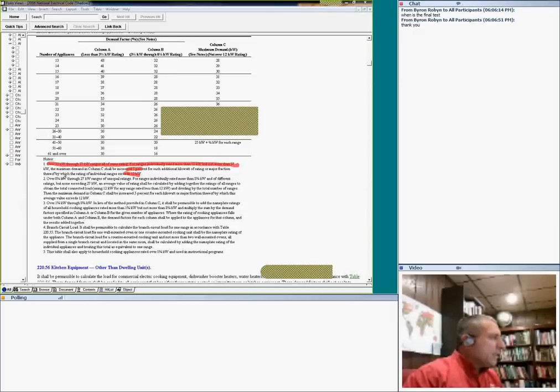If they are different sizes, you average them and you increase the average 5% for every kW larger than 12. Anything less than 12, make it 12. Average them, then increase by 5% for however many kW the average is higher than 12. Really cool, and I don't want to get into it. Sometimes, based on this, they allow you to use B or C, and use the one that gets you the more demand.